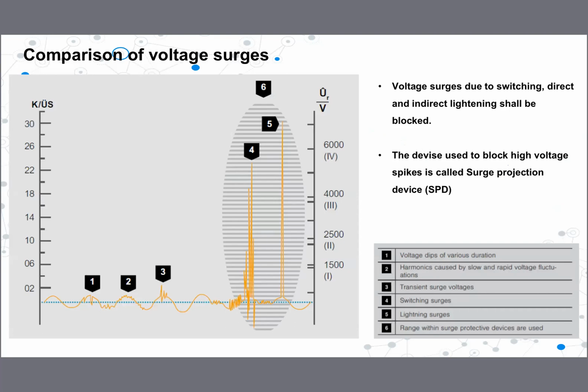Now let's look at a comparison of these different types of voltages, right? Transient voltages. Now, in the healthy case, our waveform is something like this. It's a smooth sinusoidal waveform, and there can be dips in the waveform due to certain reasons. But this voltage dip doesn't cause any serious damage, right? Voltage drops suddenly and comes back to the normal level. And also there can be ripples in the voltage waveform in this area, right? Those are not spikes, but ripples. The reason for this is harmonics, right?